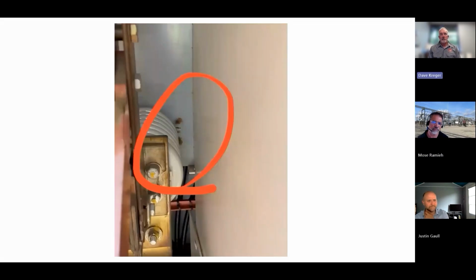Well, the cleanliness and the environment that your switchgear is in, especially if you're in a facility that generates a lot of dust - and some of it can be conductive dust. Simple things like keeping the switchgear clean, keeping the filters clean in the switchgear, or something as simple as keeping the weeds cut down in a substation. Those aren't just to make it look pretty - that is to extend the life of the equipment.